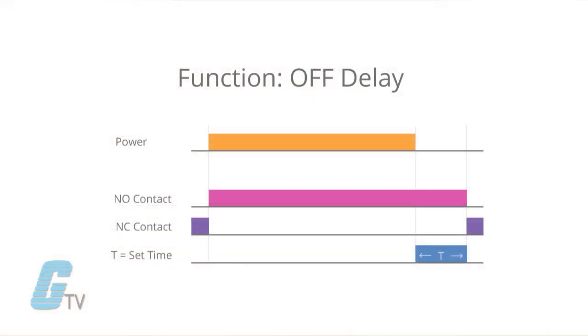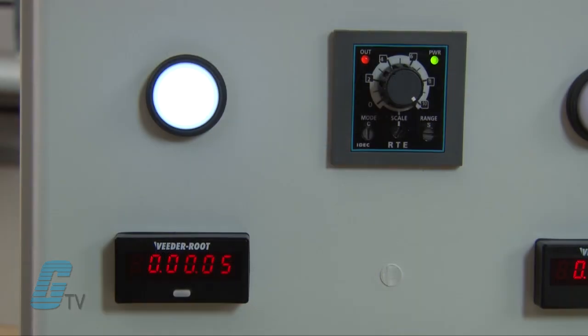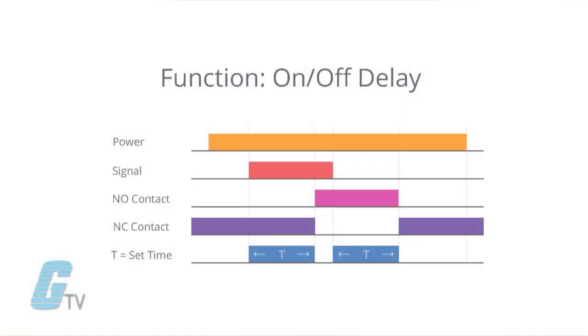Off delay timers begin timing when power is removed or when triggered by a signal. The contacts will change from an on state to an off state after the time has elapsed. This should not be confused with an on off delay timer, which can be used with signal start timers.